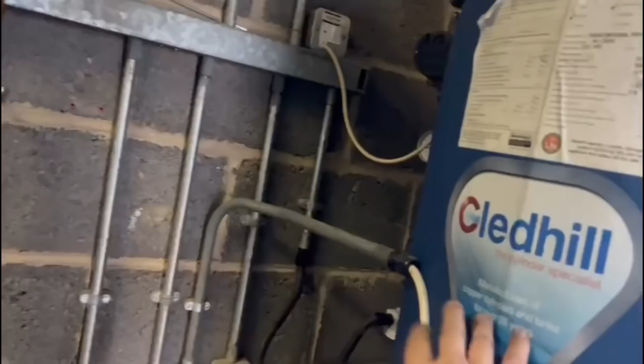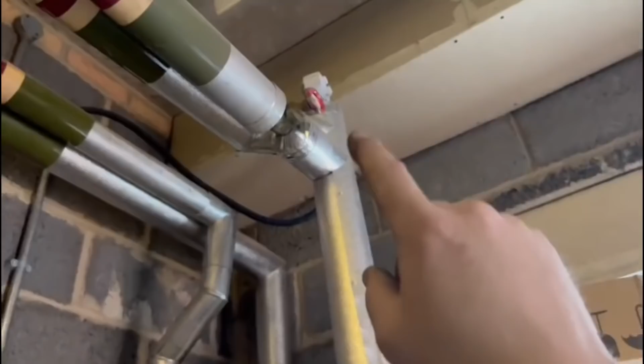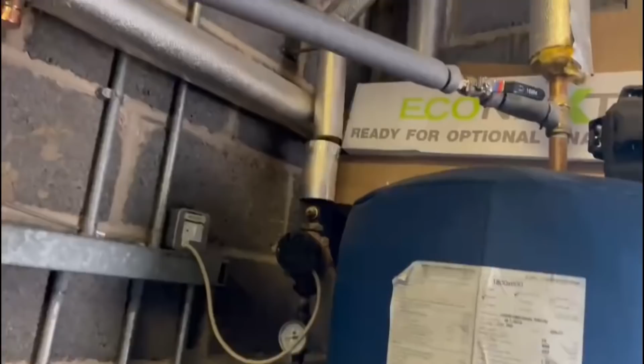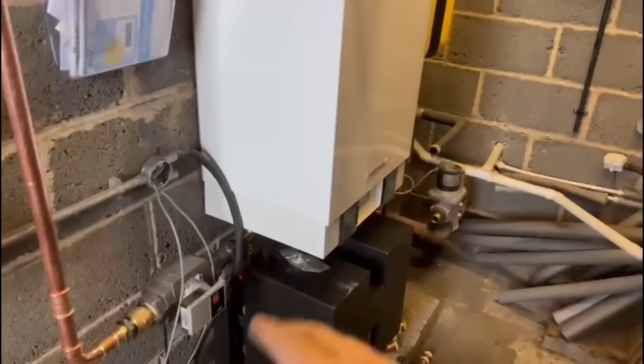I then need to get a sensor to the temperature of this, so the boiler's got a target and a live set point. Now I have got a sensor up there, which is probably too far away for this, so I might cut one into the cylinder, and then again run one of these cables I've got on there to that sensor. I'm going to reuse that, find it out of the containment, find where it goes, and then I'll link that into the boiler. So the boiler is telling which pump to come on using domestic hot water priority on weather compensation. So all of this electrics is going to be redundant.